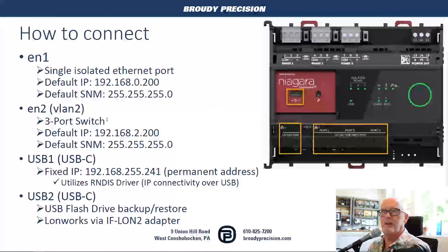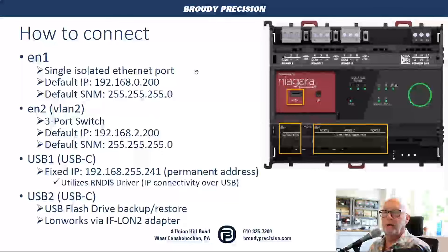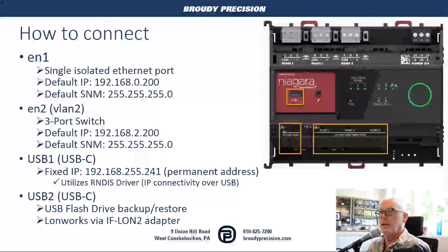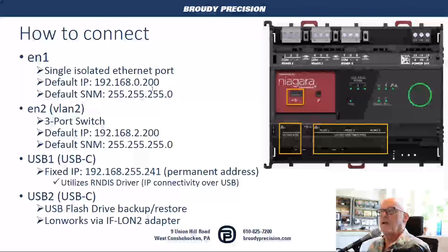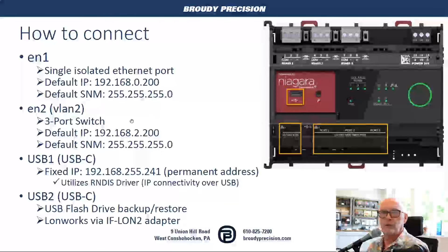With the Optimizer Advanced, the best thing to do is start with how to connect to it and how to establish the Shell Connection. On the Advanced Controller, you're going to find there is an Ethernet 1 (EN1) and an EN2. EN1 is a single isolated Ethernet port with a default IP address of 192.168.0.200. The second port, EN2, also known as VLAN2 inside the controller, is a three-port switch with a default IP address of 192.168.2.200.